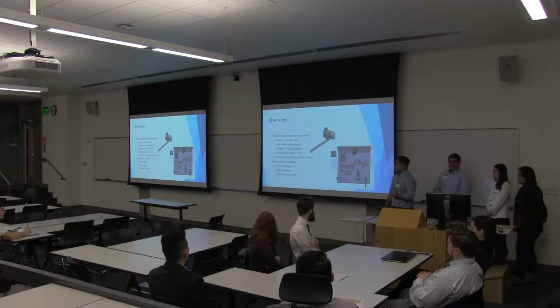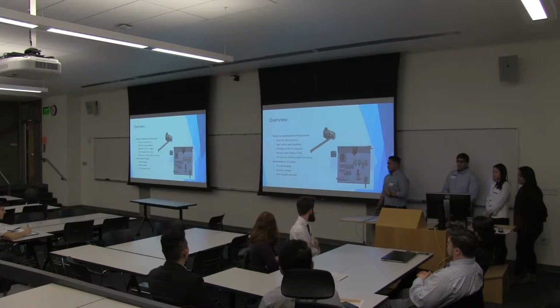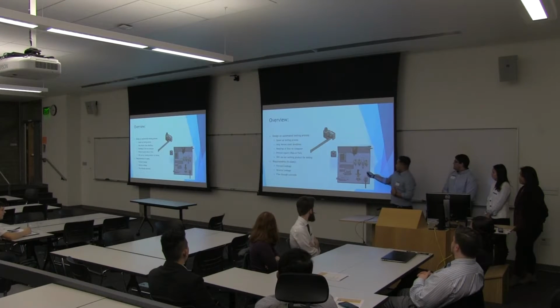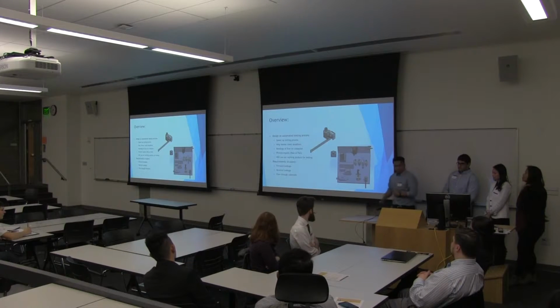They've asked us to check the forward leakage, the reverse leakage, and the flow through the solenoids inside our unit under test. The 2 solenoids are located right there, and the unit under test will be placed here on our board.